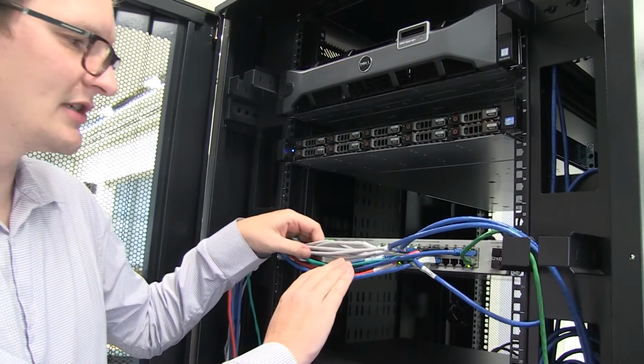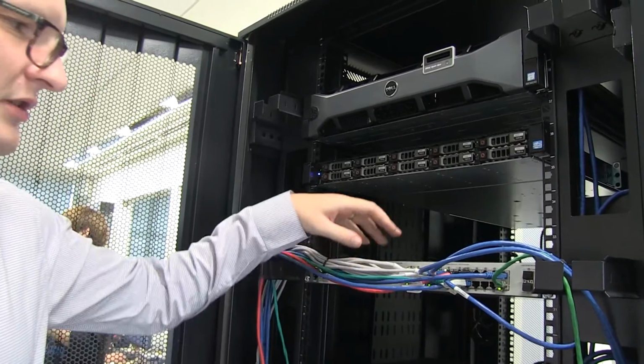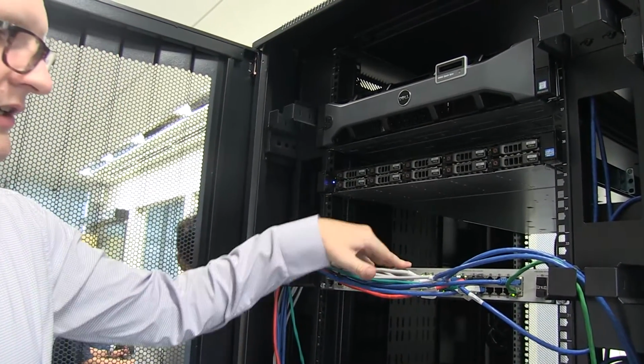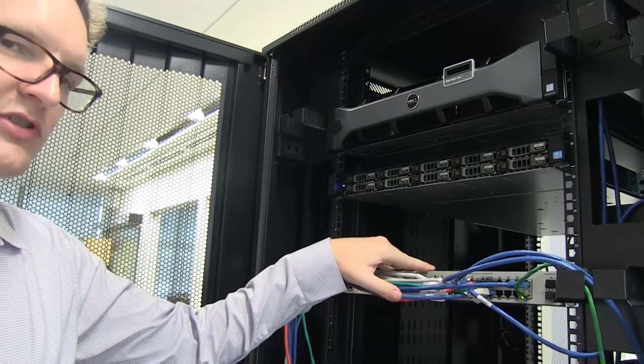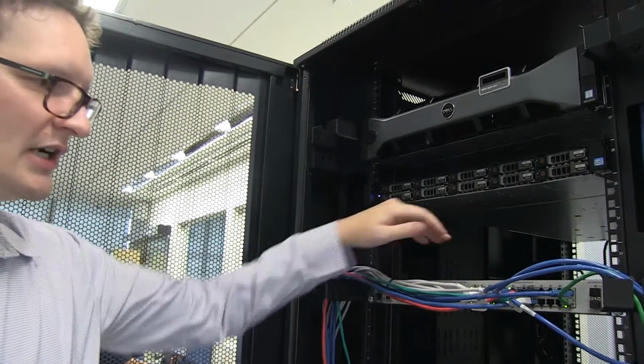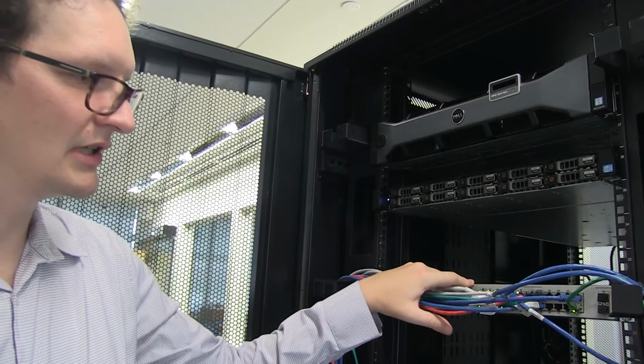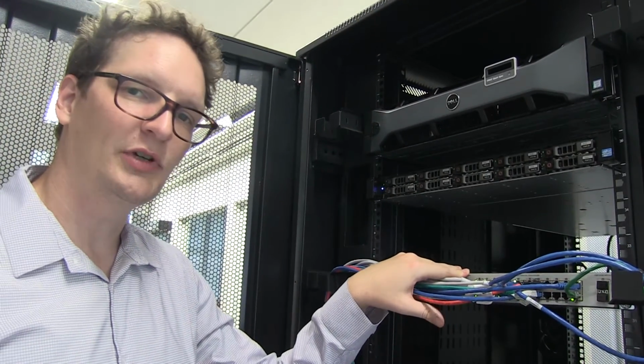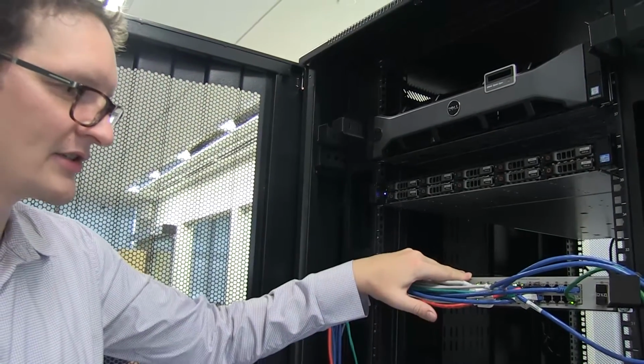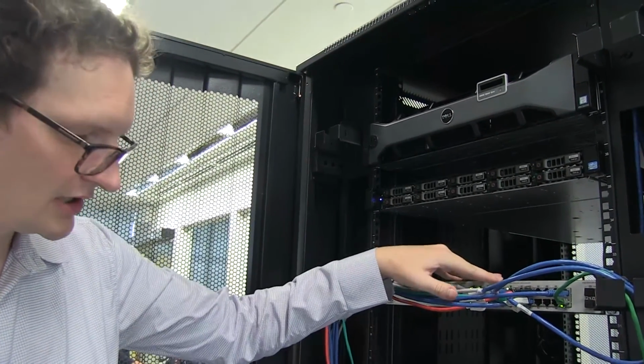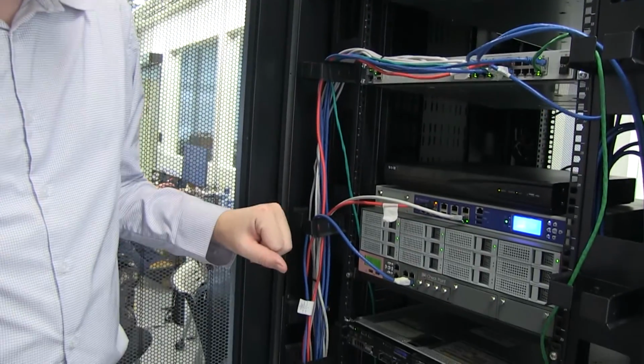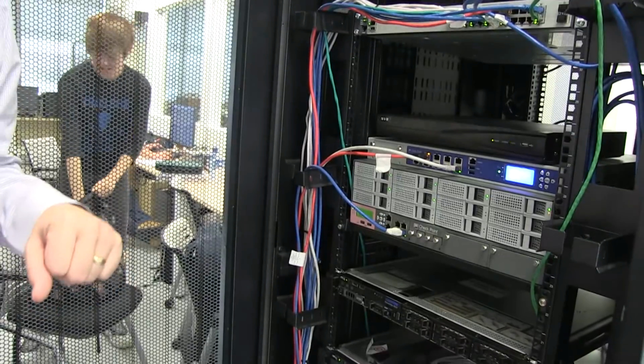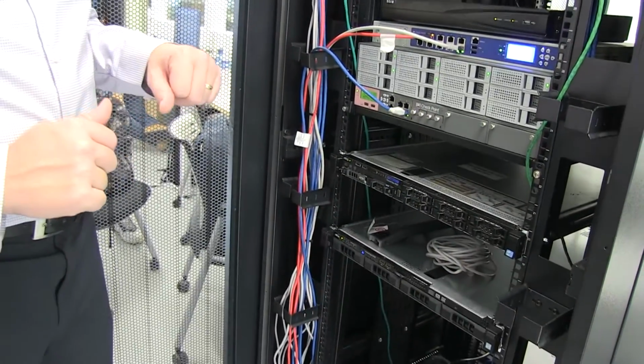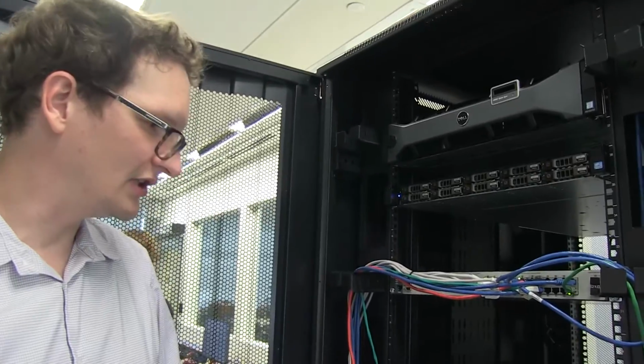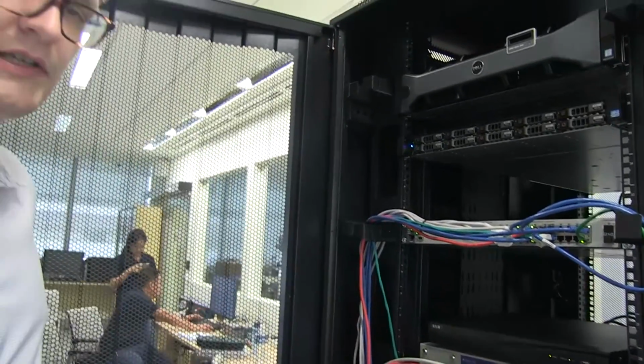You see here all the gray cables are essentially connections coming directly from the PLCs. So the PLCs are using the switch to communicate with each other. In addition, we have the SCADA workstation and the storage connected to this. The HMI is connected to this as well, and we then have 4 ports which are essentially providing a copy of all the network traffic that is being exchanged for later analysis. This copy of the traffic is fed into the other servers, and on these servers we have a number of virtual machines running intrusion detection software, for example. We also have external collaborators. For example, this company here is setting up its own intrusion detection system to analyze the traffic that is exchanged in the plant in real time.